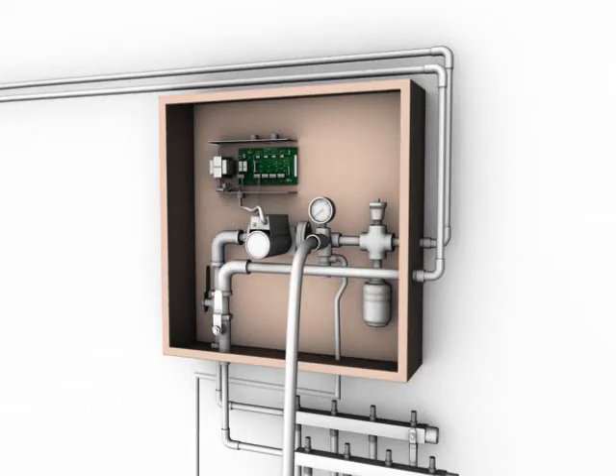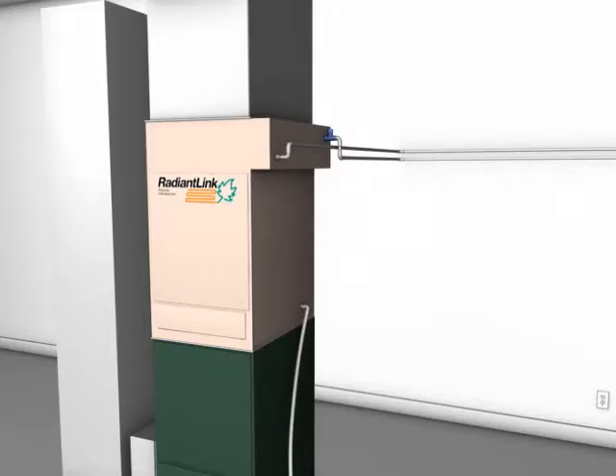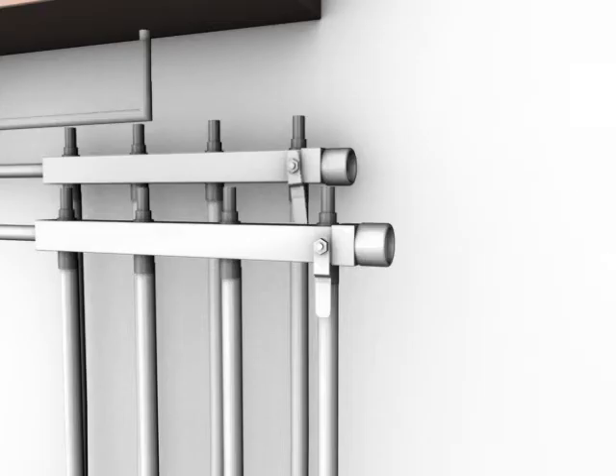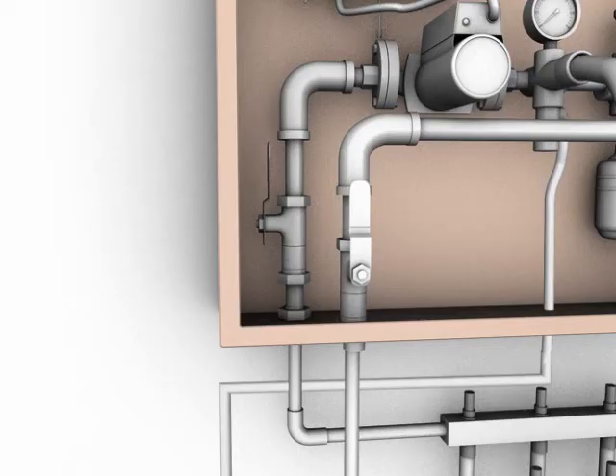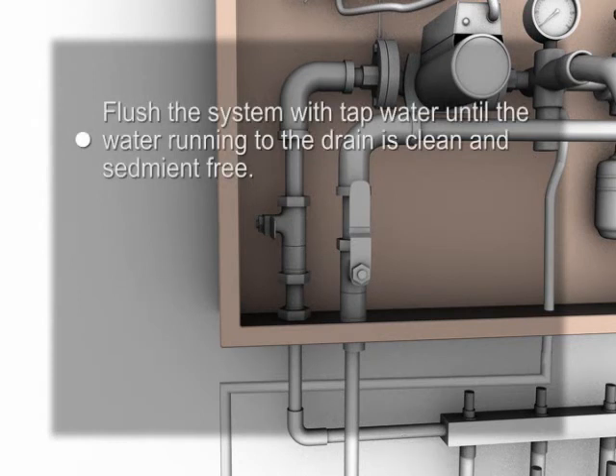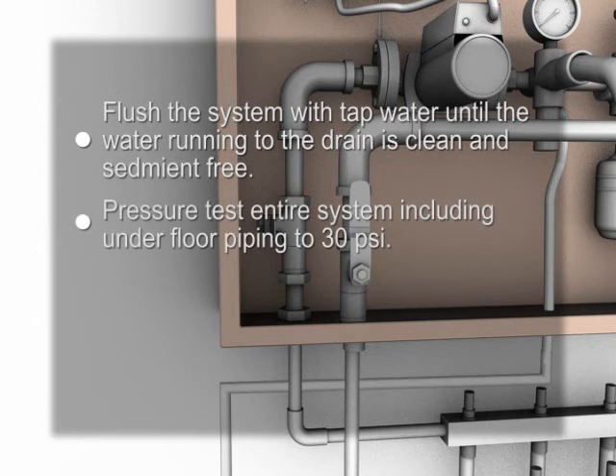Fill the system while bleeding air from the air vent at the system high point. Open the drain valve on the radiant floor supply manifold and provide a temporary drain hose to the nearest floor drain. Close the valve in the control panel in the radiant floor supply line. Using a garden hose, flush the system with tap water until the water running to the drain is clean and sediment-free. Pressure test the entire system, including underfloor piping, to 30 psi.